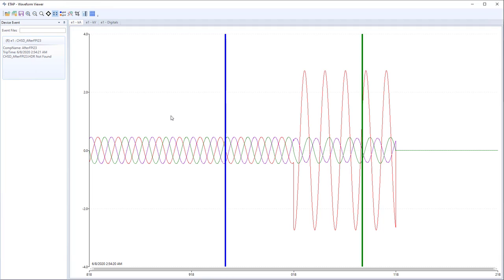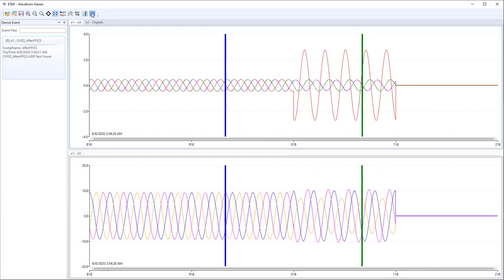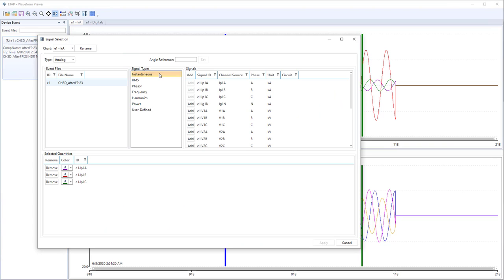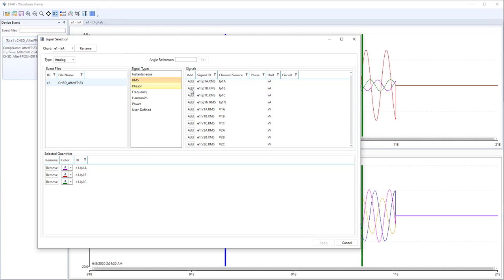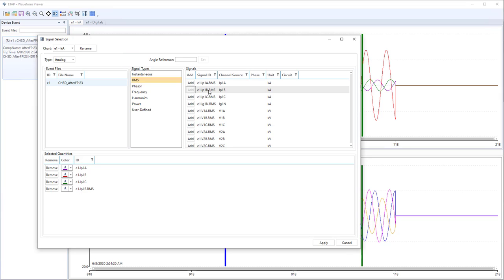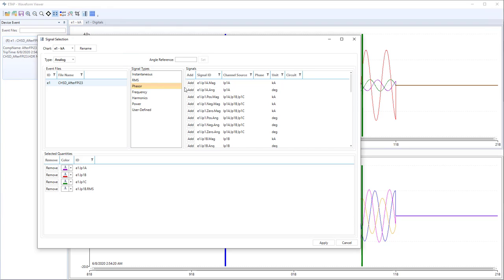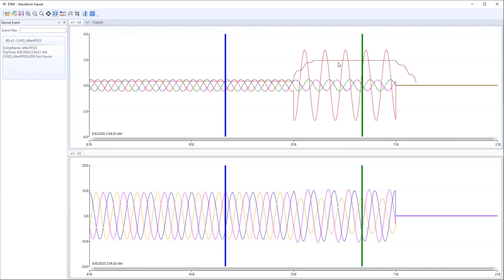For a more detailed look into the waveform, we can use the Waveform Viewer. The Waveform Viewer allows us to add plots of different calculated results for each signal. The signal types are listed, including instantaneous that we previously viewed, RMS, which ETAP calculates, as well as other results such as frequency, harmonics, power, and even user-defined plots that were previously created. We can select to show instantaneous as well as RMS, and the measurements can be combined into a single plot or viewed individually.